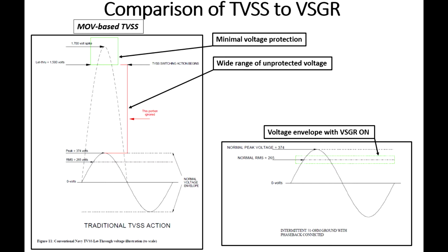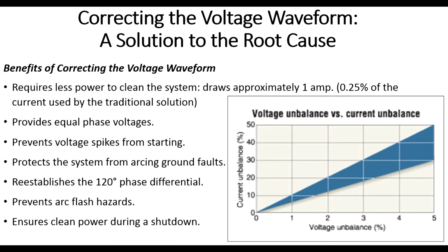On the right, we see a stark comparison of the operating voltage envelope using a voltage stabilizing ground reference. You'll see that the entire voltage change is minimal. The voltage cannot exceed the nominal peak value. One of the significant benefits of keeping the voltages balanced is that with balanced voltage you have balanced current. Here's a graph from the IEEE showing voltage imbalance causing current imbalance. A 5% voltage imbalance can cause a 30 to 50% current imbalance in a motor. A 3% current imbalance in a motor can cause it to run excessively hot. So voltage unbalance is a very, very critical feature.